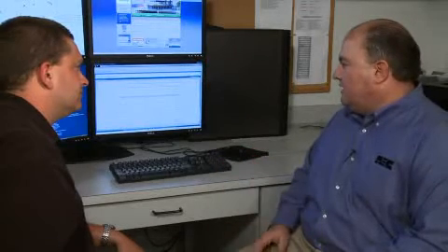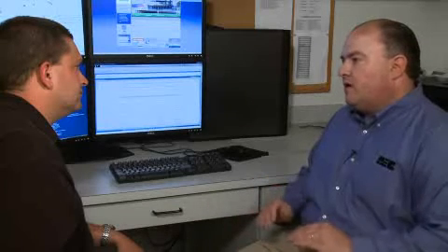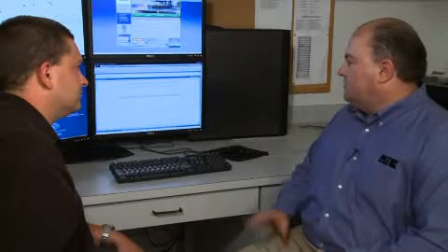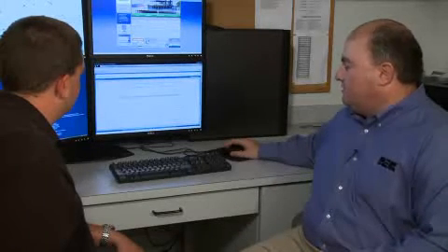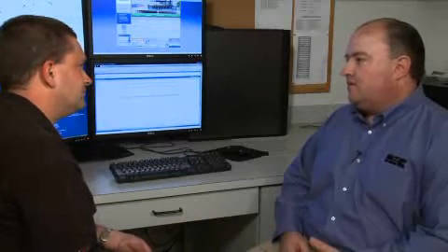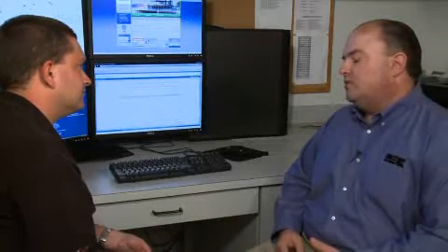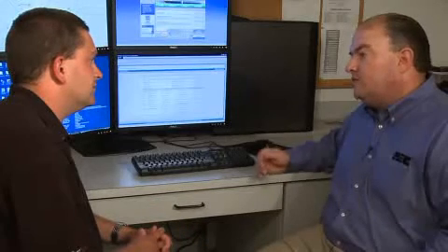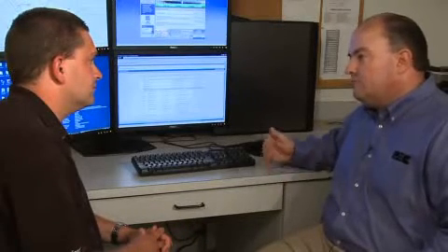This is a downline, single-phase recloser that's operating. You don't have any communication with it — it's a hydraulically controlled device. So we most likely would not know it if we didn't have these capture files from the DFA. So if left unchecked, will there be an outage? We have seen time and time again that these things usually do produce an outage. So we can take these pieces of information and many times really narrow down the area where we need to look to find the fault. The system is making your field crews pretty happy then? Yes, we've saved a significant amount of time searching for troubled faults.